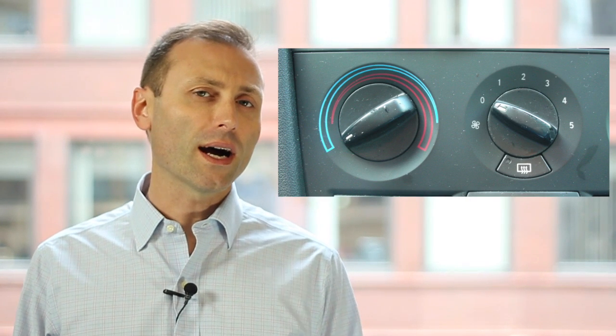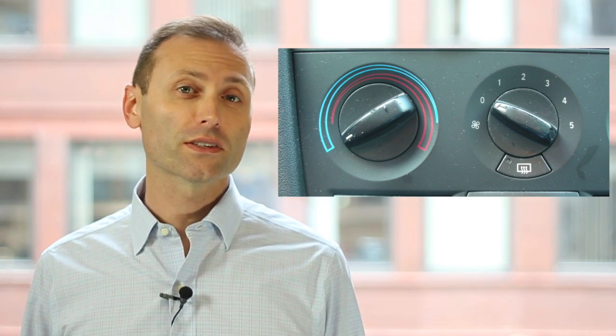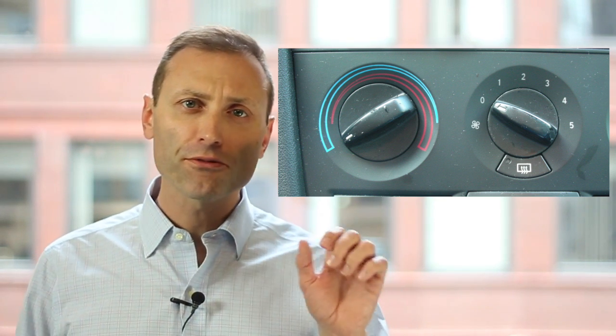When you get into a hot car and blast that air conditioning, eventually you'll start to feel cold. At that point, most people turn down the fan to make the temperature more comfortable. A VAV system does the same thing. It varies the amount of air being supplied to a space to maintain the temperature set point.